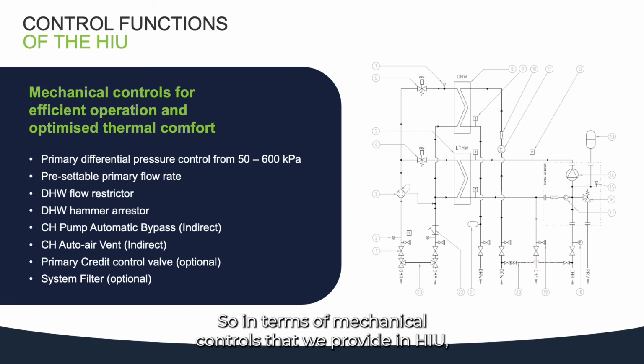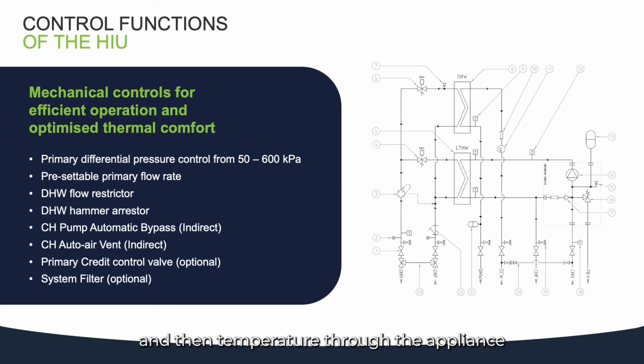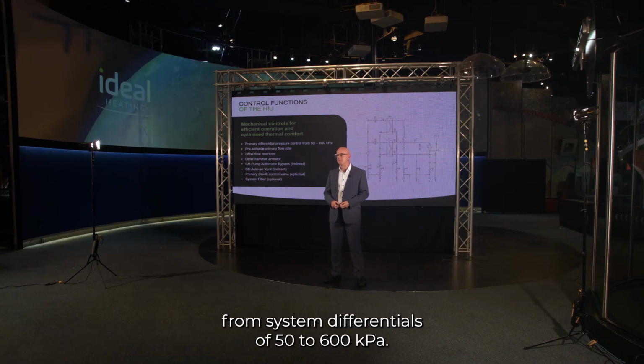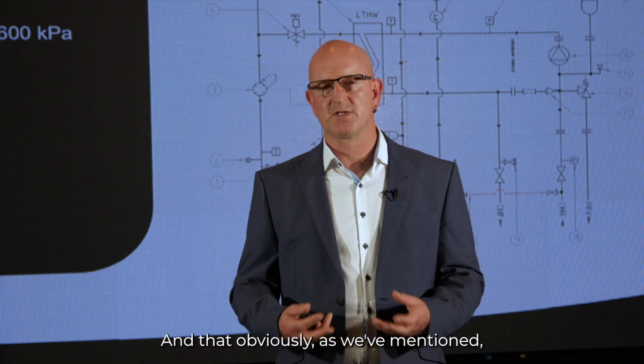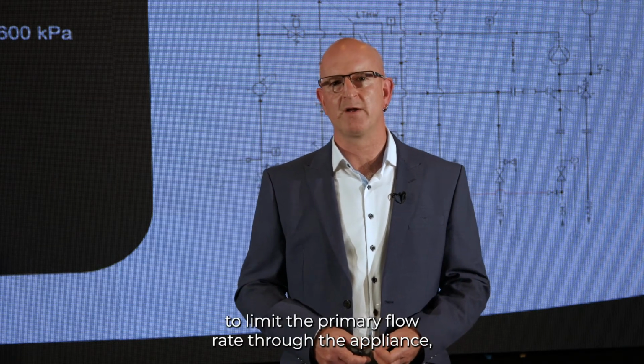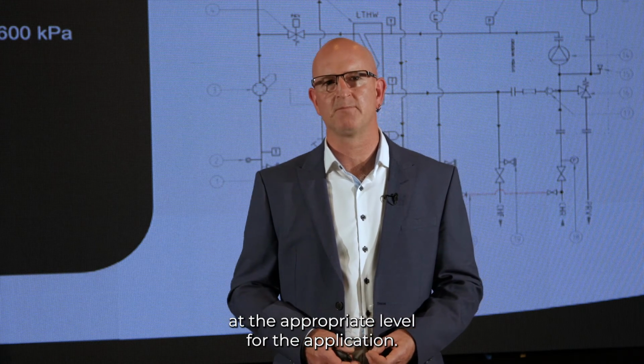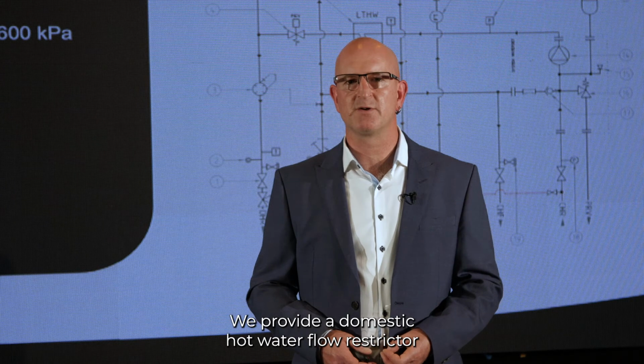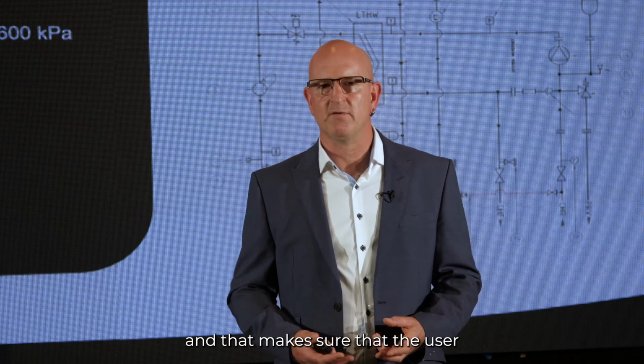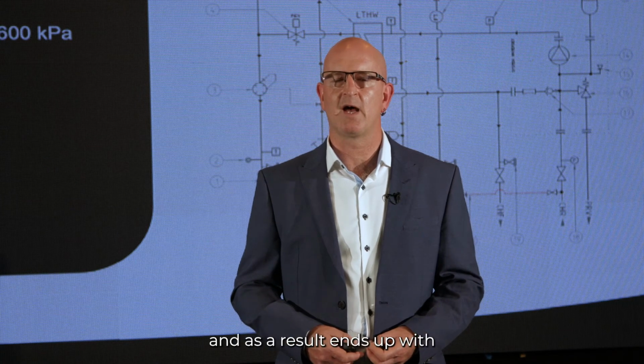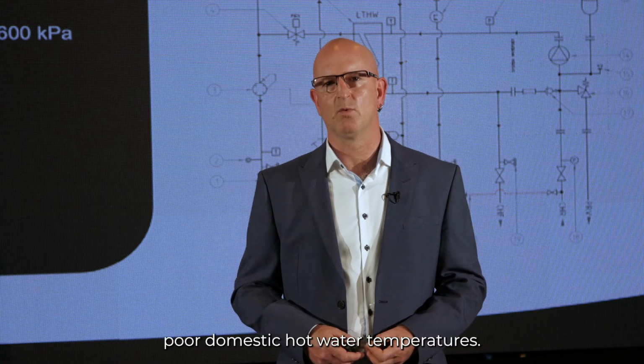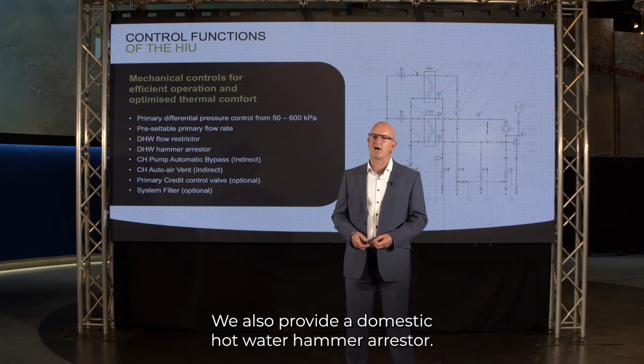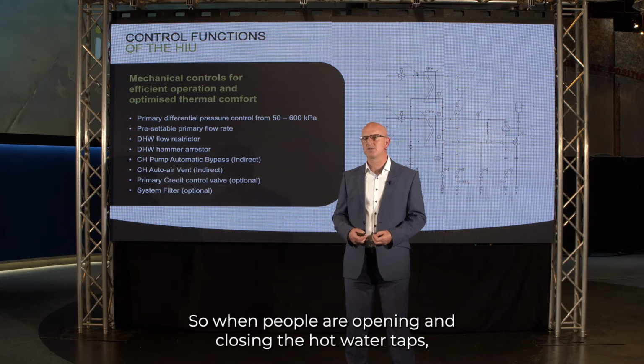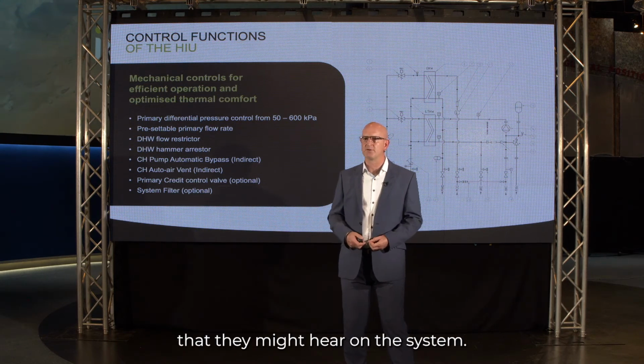So in terms of mechanical controls that we provide in the HIU, we've obviously got primary differential pressure control valves, which give us the opportunity to control flow and then temperature through the appliance from system differentials of 50 to 600 kilopascals. And that, as we've mentioned, can be presettable to limit the primary flow rate through the appliance at the appropriate level for the application. We provide a domestic hot water flow restrictor on the domestic hot water side, and that makes sure that the user isn't trying to overflow the appliance and as a result ends up with poor domestic hot water temperatures. We also provide a domestic hot water hammer arrestor, so when people are opening and closing the hot water taps, it's going to limit the amount of noise that they might hear on the system.